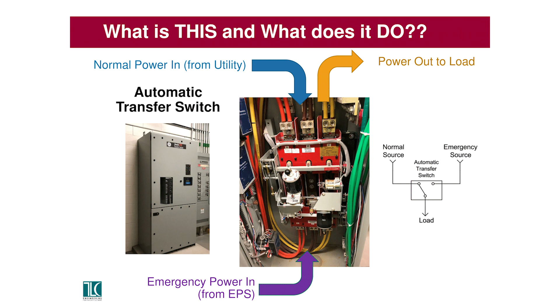And then automatic transfer switches are where all the fun happens. This is the switch that physically switches between normal power, the utility power, and emergency power. So you've got normal power coming in, emergency power coming in, and the load going out. That's what it looks like on the inside. You'll see some more pictures, and they're represented by this very clever diagram here.